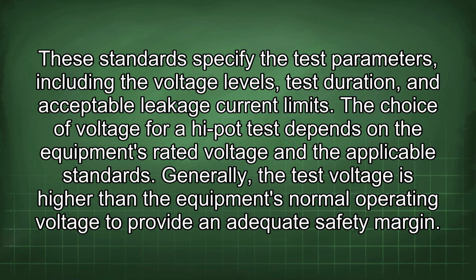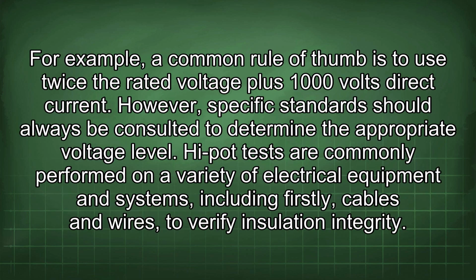The choice of voltage for a hi-pot test depends on the equipment's rated voltage and the applicable standards. Generally, the test voltage is higher than the equipment's normal operating voltage to provide an adequate safety margin. For example, a common rule of thumb is to use twice the rated voltage plus 1000 volts direct current. However, specific standards should always be consulted to determine the appropriate voltage level.